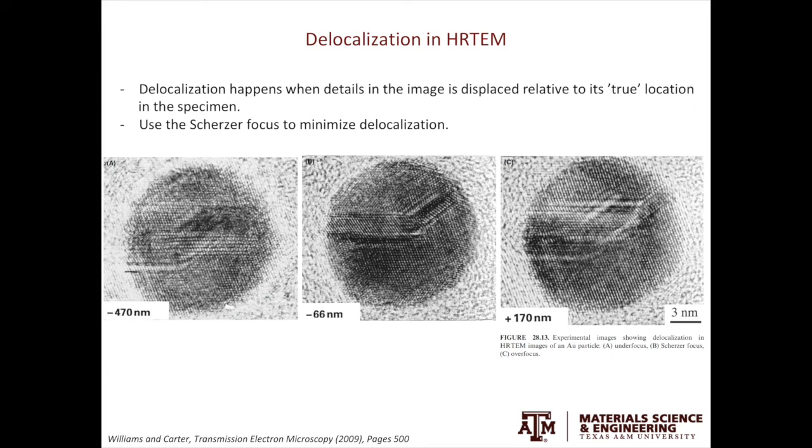Another complication in high-res TEM is called delocalization. Delocalization happens when details in the image are displaced relative to their true location in the specimen. The image in the middle is set at the Scherzer defocus. While the one on the left and the one on the right, they are out of focus. Because of the large value of defocus, in the regions where it doesn't have the gold nanoparticles such as here, you see lattice fringes. Also, the location of the planar defects in the gold nanoparticles are also displaced. The rule of thumb is always use the Scherzer defocus when doing high-res TEM to minimize the delocalization.